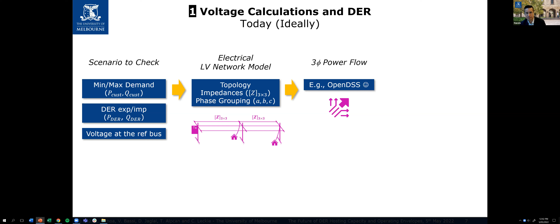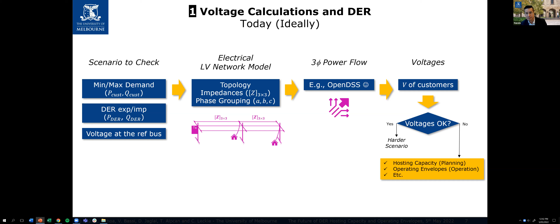And then, of course, you check the voltages because you run a power flow, you check the voltages, and if they're okay—say you're running a hosting capacity analysis—you would put a harder scenario, like more houses with photovoltaics. But if the voltages are not okay, it means you've reached what you wanted, so that's your hosting capacity. The same process applies for operating envelopes, and the same process applies for anything else.